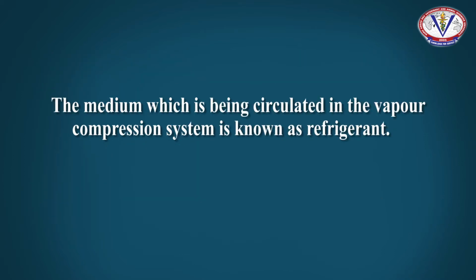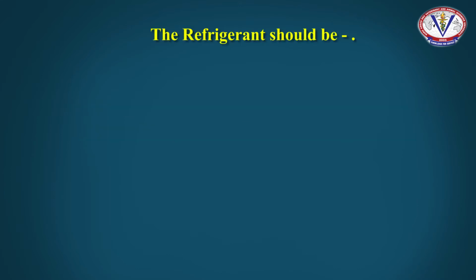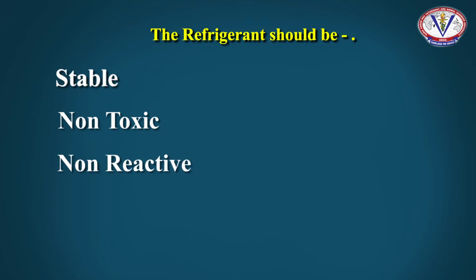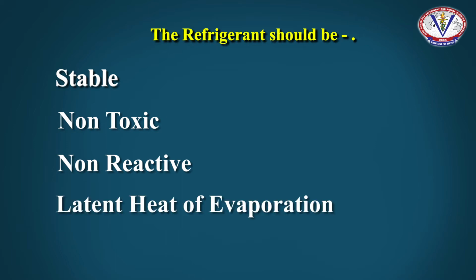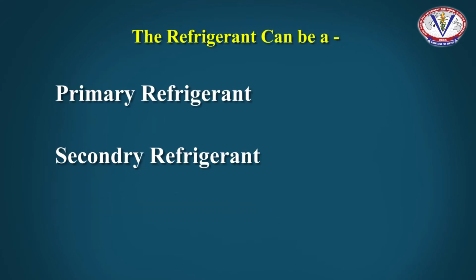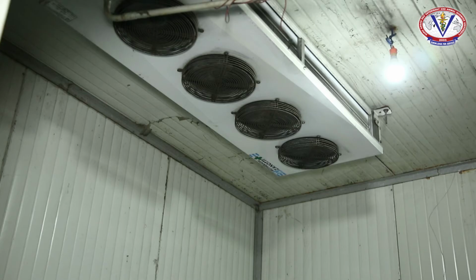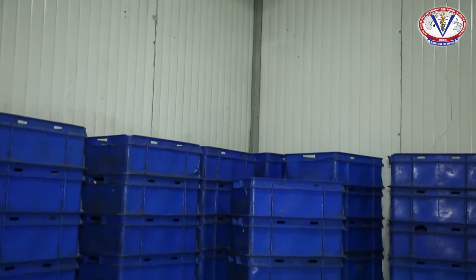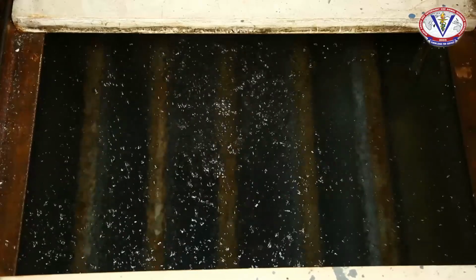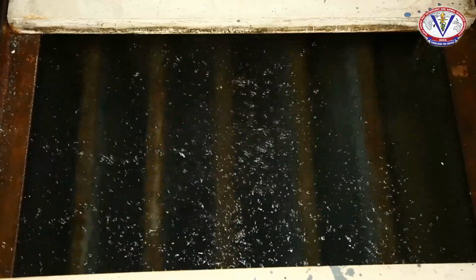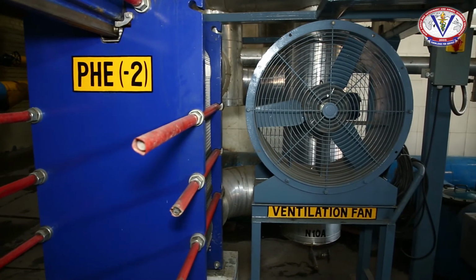The medium which is being circulated in the vapor compression refrigeration system is known as refrigerant. Refrigerants should be stable, non-toxic, and non-reactive with the materials used for the construction of the components. They must have a sufficiently high latent heat of evaporation so that the refrigeration effect can be maximized. Refrigerants can be primary or secondary. The primary refrigerants extract the heat in the evaporator and cool the environment, whereas the secondary refrigerants are first cooled by the primary refrigerants and then used to lower the temperature of the commodity or the space.